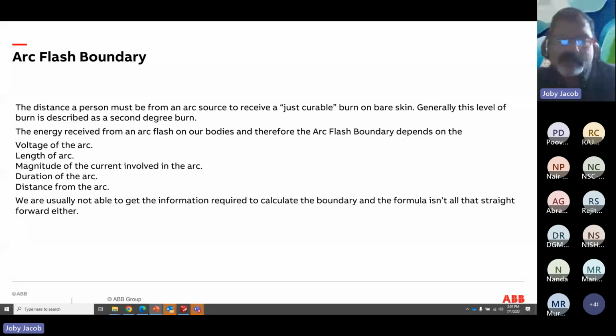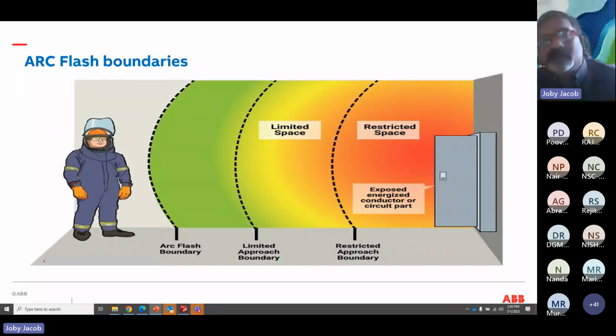The energy received from an arc flash depends on the following parameters: the voltage, the length of the arc, the magnitude of the current involved, the short circuit current in that arc, the duration of the arc, and the distance where you are standing from the arc. We are usually not able to get the information required to calculate the arc flash boundary. If you have done a short circuit study, yes, probably you can get all these parameters, and we can use an arc flash calculator. So a little bit on the arc flash boundary.